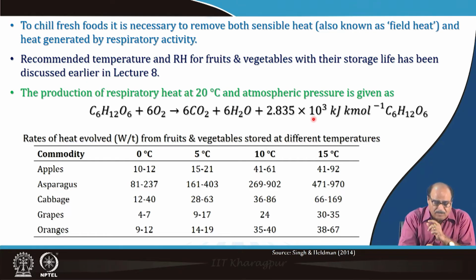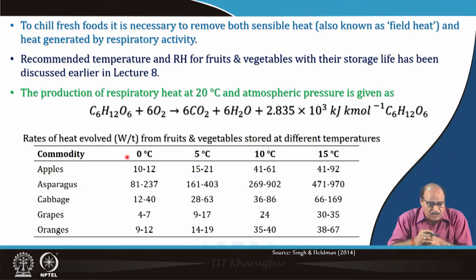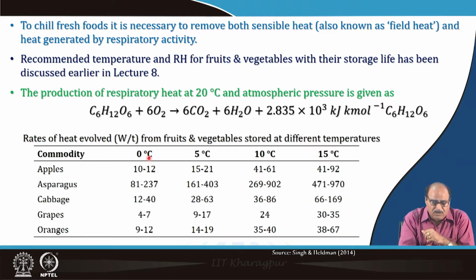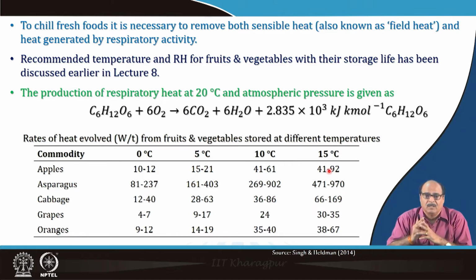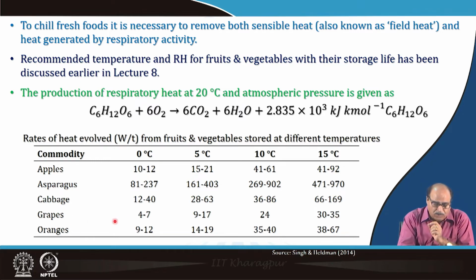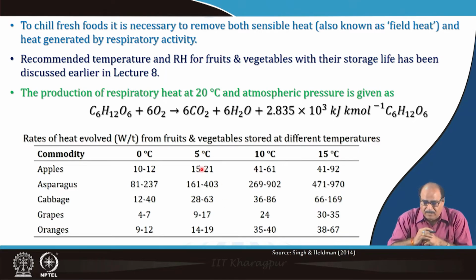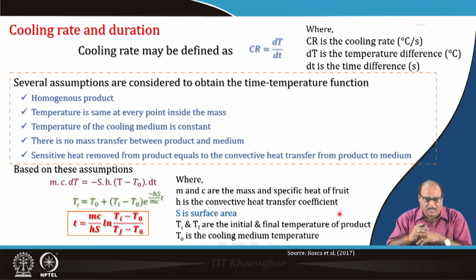This table gives the rates of heat evolved in watts per ton from fruits and vegetables stored at different temperatures. For example, apples stored at 0 degrees Celsius produce 10 to 12 watts per ton, whereas at 15 degrees Celsius they may produce 41 to 92 watts per ton. Grapes produce 4 to 7 watts per ton at 0 degrees Celsius, 9 to 17 watts per ton at 5 degrees Celsius, and 30 to 35 watts per ton at 15 degrees Celsius. These are important commodities showing the rate of heat evolution at different temperatures, useful for calculating the refrigeration load.